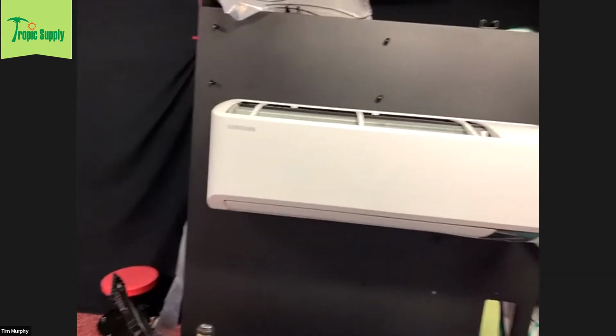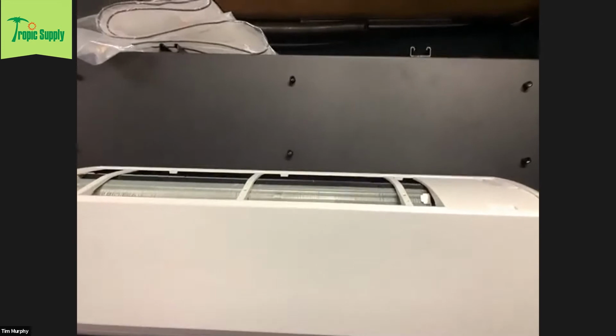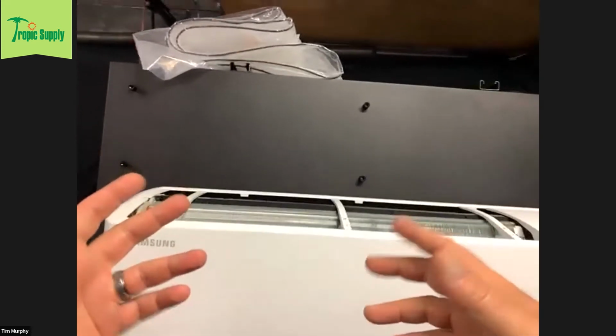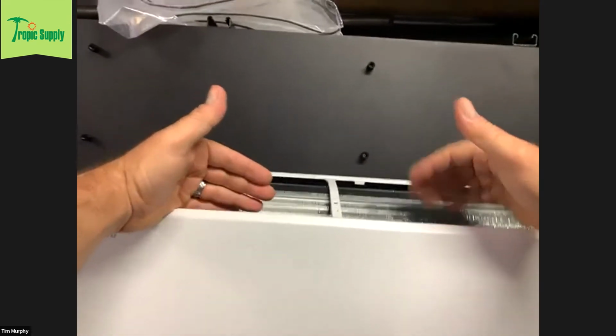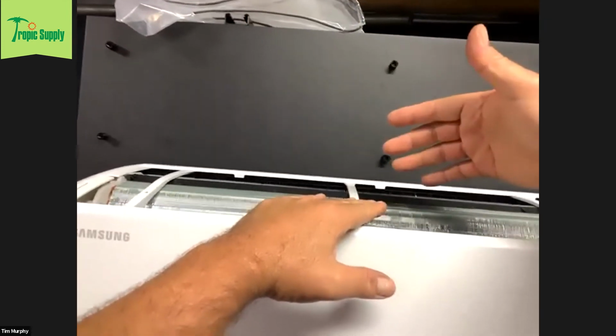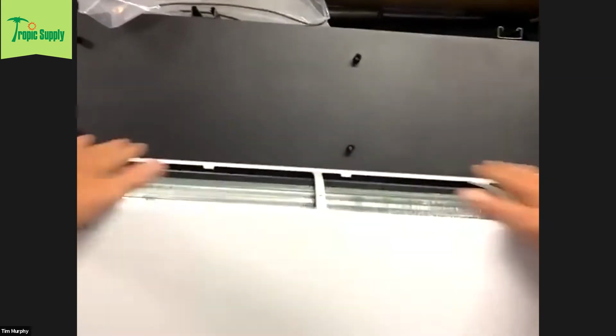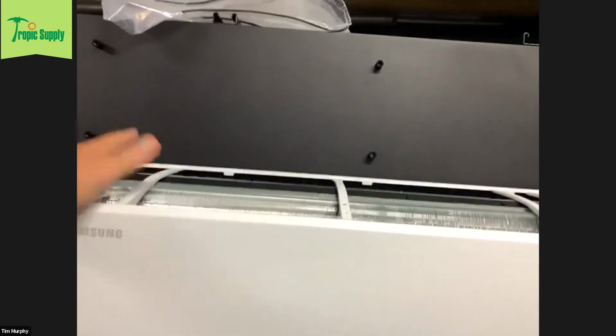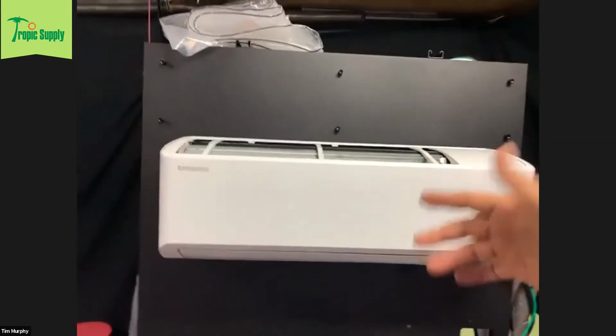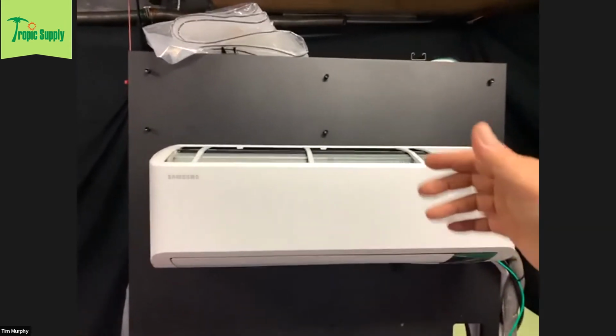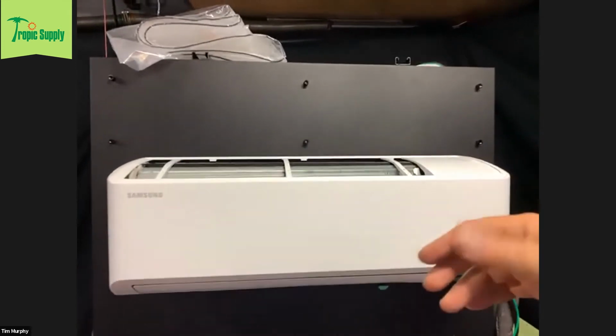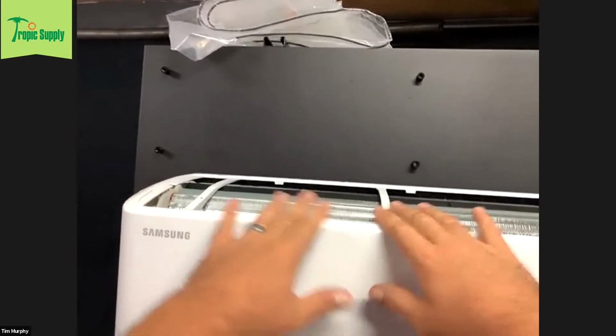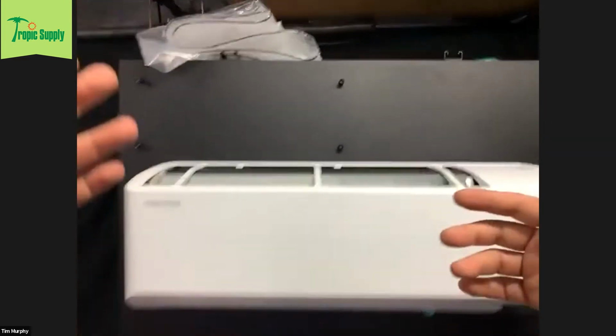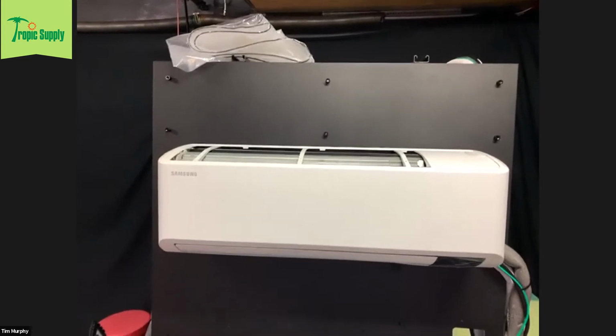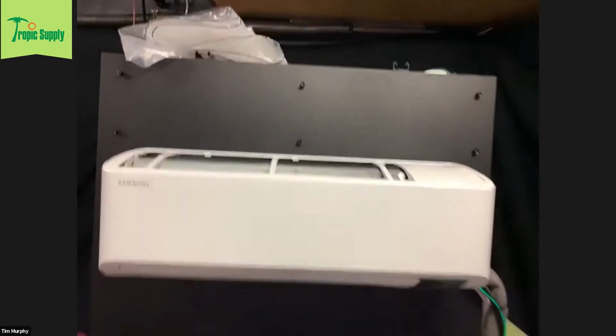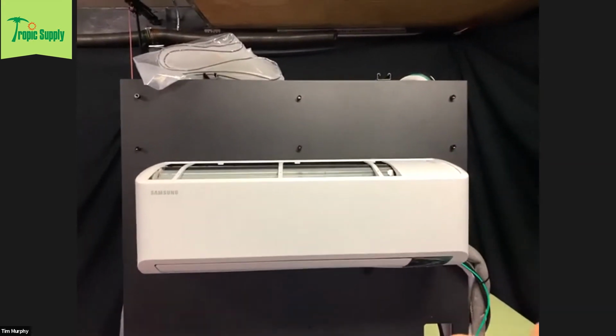Another thing I've seen in the past: at a house, or maybe a restaurant, a customer or even a contractor will add something over the filter where the air draws in. You want a minimum of 6 inches above this unit to let the air circulate through it. Sometimes they'll take a hog's hair filter or some kind of dust lock filter, cut it, and put it on top as an additional filter over the existing one provided by Samsung or whatever mini split you're using. These are not high static systems, so anything that prohibits the air from flowing the way it was designed can definitely cause issues and problems in the future. If you see that on any mini split system, it's important to tell the homeowner they shouldn't be doing that, it's really not recommended.